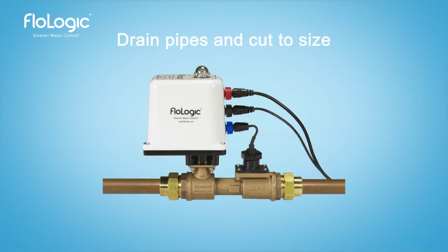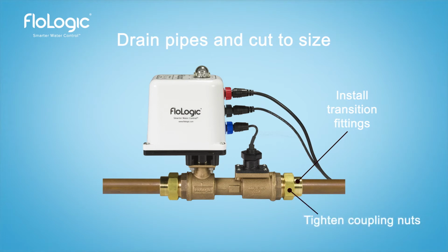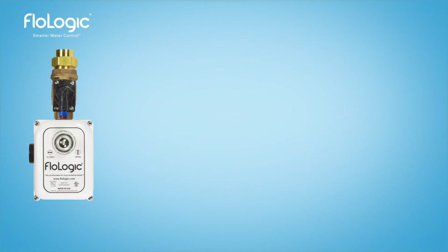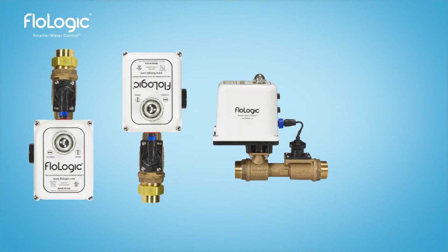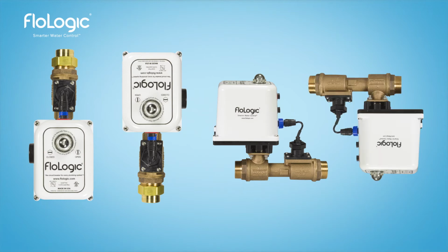Turn off the supply and drain the pipes. Cut the pipe and install the valve according to the dimensions noted in the installation instructions. 1-inch valves connect to the female 1-inch NPT transition fittings. 1 1/2 inch and 2-inch valves have brass sweat fittings matching the valve size. The valve can be oriented vertically, flowing up or down, and horizontally in an up-facing or down-facing orientation.